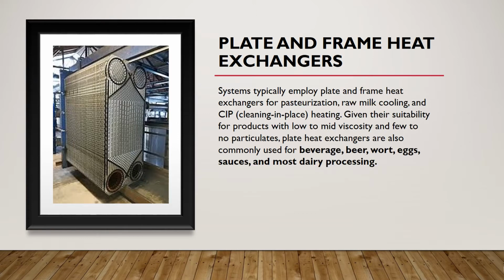Systems typically employ plate and frame heat exchangers for pasteurization, raw milk cooling, and cleaning in place heating. Given their suitability for products with low to mid viscosity and few to no particulates, plate heat exchangers also are commonly used for beverage, beer, wort, eggs, sauces, and most dairy processing.